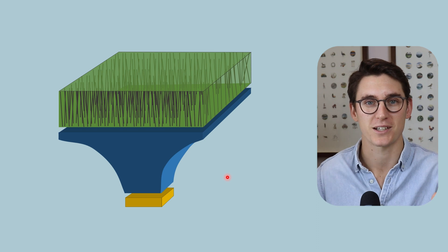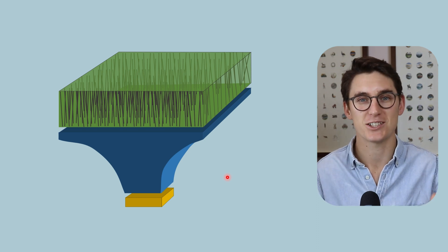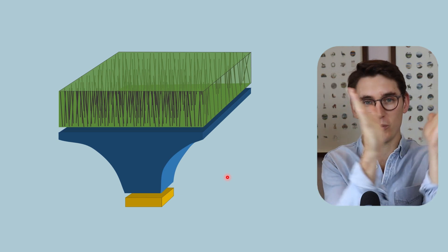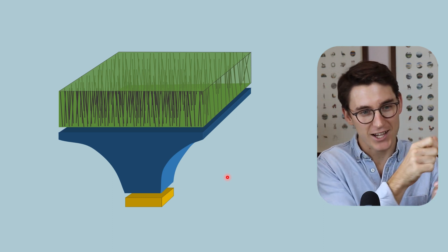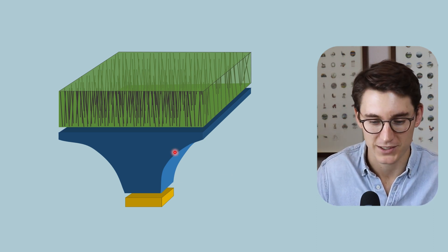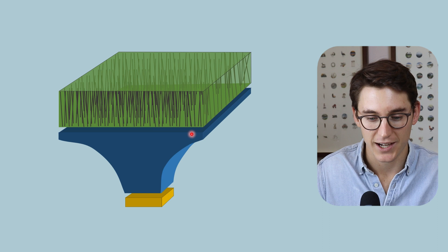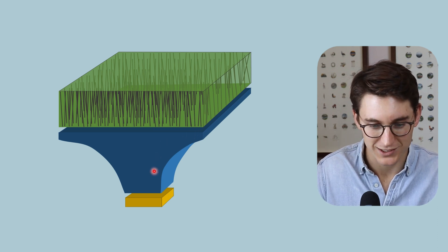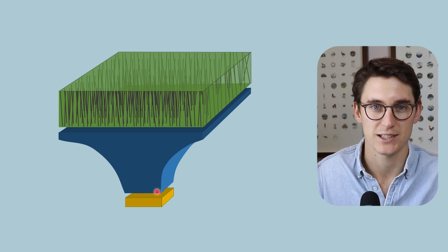The first is fiber optic coupling. Now if you're an 80s or 90s baby like me, you would have had those lamps next to your bed with those fiber optic lights. And as you move that plastic wire, the light changes with that fiber optic wire. It's a similar concept here. The light striking this portion of the fiber optic coupling will be funneled down towards our CCD chip.